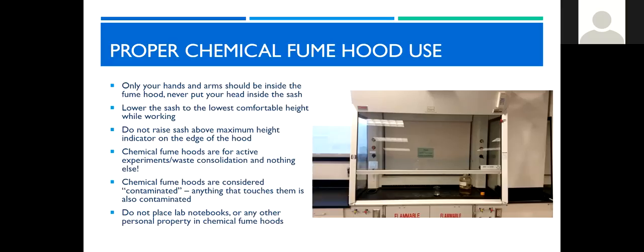In review, only ever put your hands and arms inside the chemical fume hood. Keep the sash at the lowest comfortable working height, and never raise it above the maximum height indicator on the edge of the fume hood. Fume hoods are considered contaminated with chemicals, and nothing other than the active experiment should be placed inside, including laboratory notebooks.